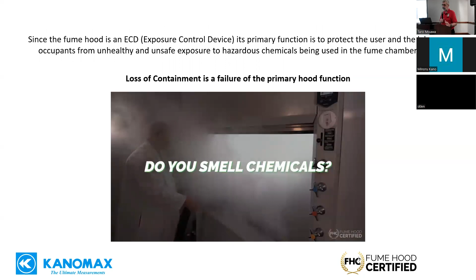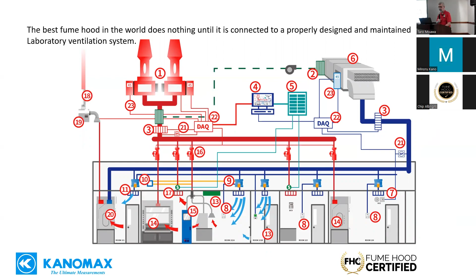So let's look at two misconceptions. The first is that fume hoods are standalone devices, and they're anything but that. A good analogy is fire sprinkler systems. If you're looking at the fire sprinklers in a lab, the most you're likely to see are the sprinkler heads in the ceiling. But for that to work, there's miles of piping and pumps and all sorts of other things. Well, the same is true with the fume hood. You can see here at the bottom, number 14 is a fume hood, but look at all that stuff it takes to make it work. So it's a very complex mechanical system, and its performance is highly dependent on what the rest of the system is doing.